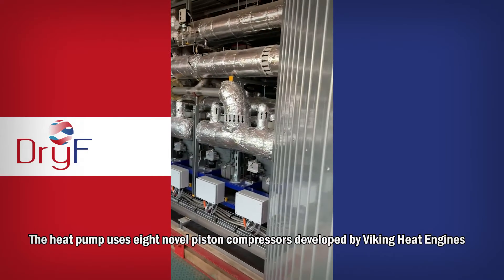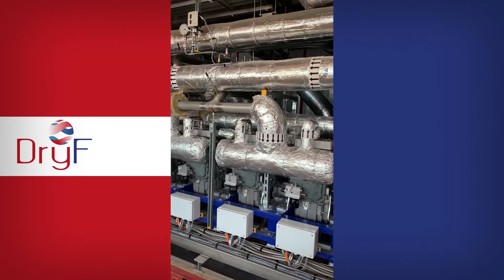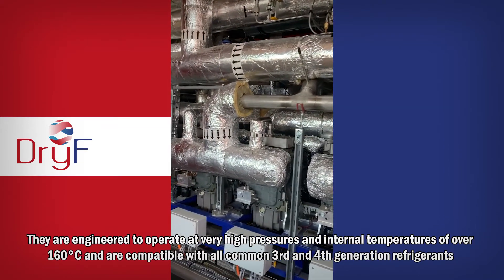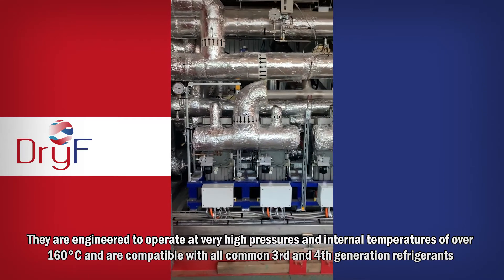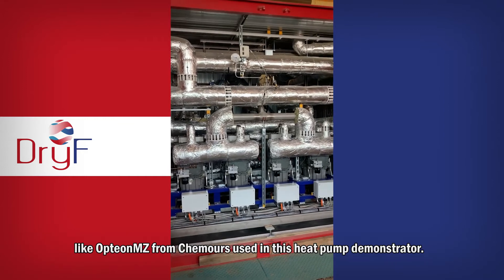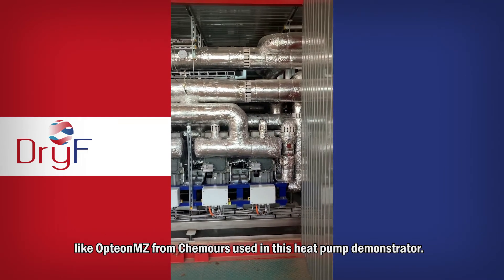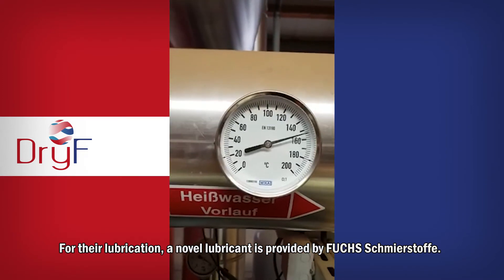The heat pump uses eight novel piston compressors developed by Viking Heat Engines. They are engineered to operate at very high pressures and internal temperatures of over 160 degrees Celsius, and are compatible with all common third and fourth generation refrigerants, like OpteonMZ from Chemours, used in this heat pump demonstrator. For the lubrication, a novel lubricant is provided by FUCHS Schmierstoffe.